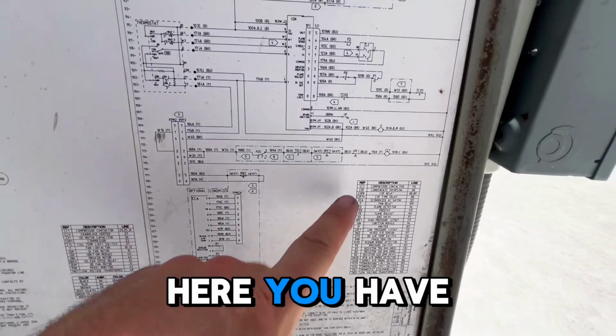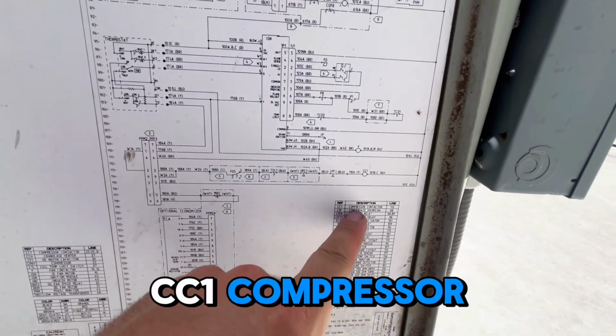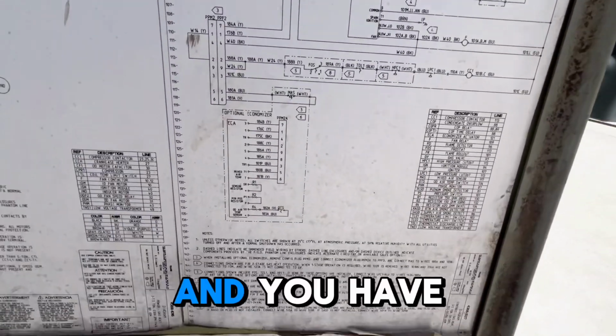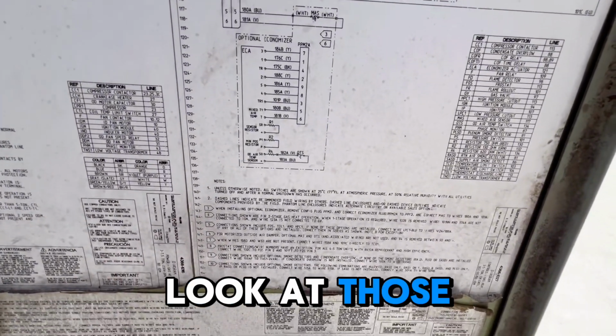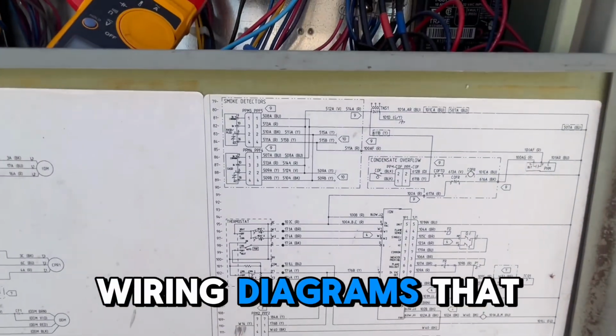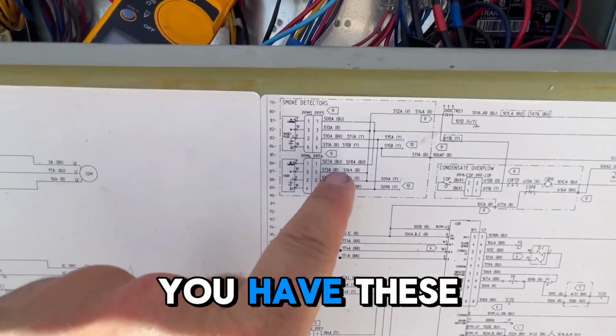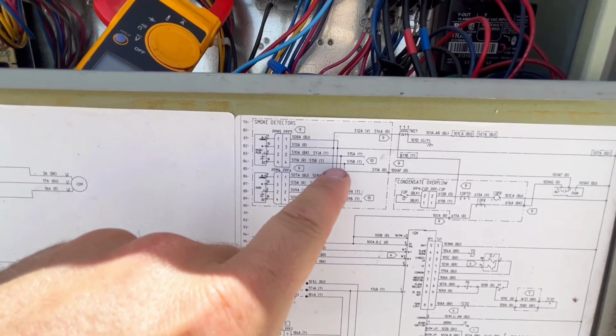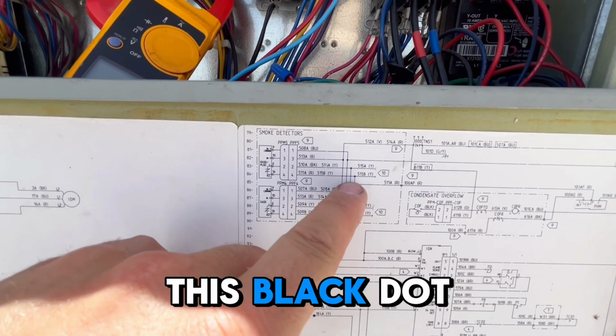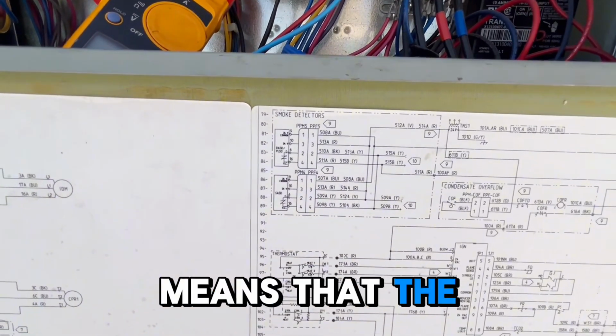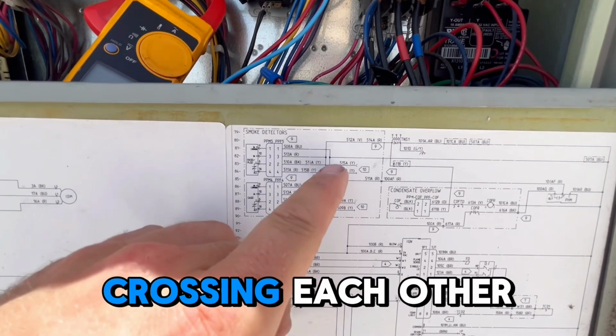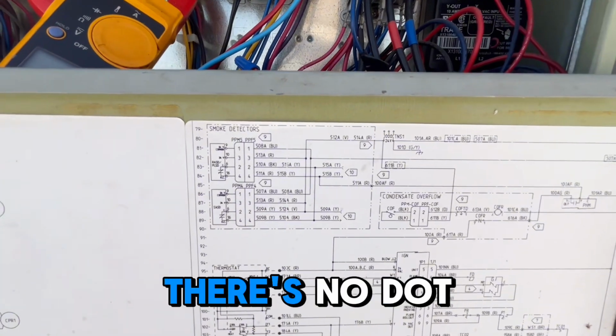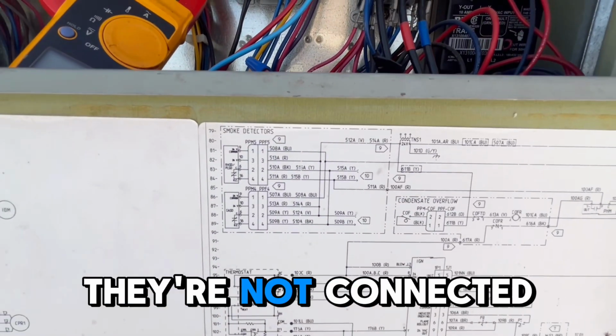And then also here you have your description, CC1, compressor contactor, for example, and you have your notes. So always look at those. One thing on wiring diagrams that is good to know is you have these solid lines, and when they're crossing, you sometimes have this black dot. The black dot means that the wires are connected. If they're just crossing each other, like over here, there is no dot, it means that they are not connected.